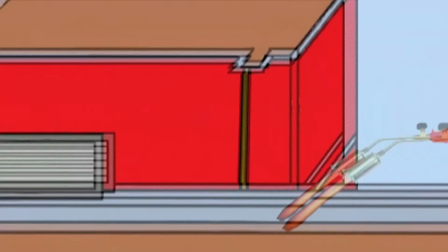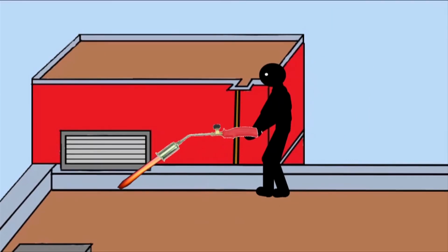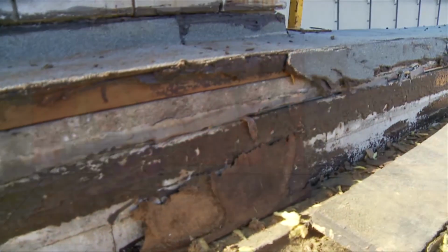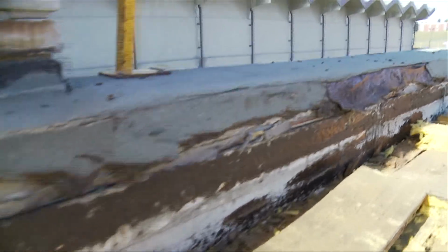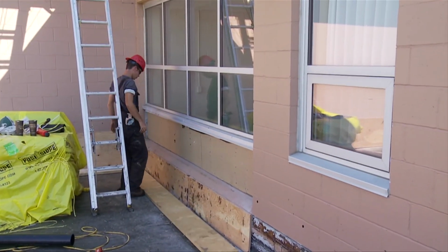Be aware of the negative air pressure created in some high-rise buildings as the result of the stack effect or wind pressure. Negative air pressure within buildings can draw the torch flame into unprotected gaps, cracks, and building voids during torching operations if they are not properly protected from the flame impingement.